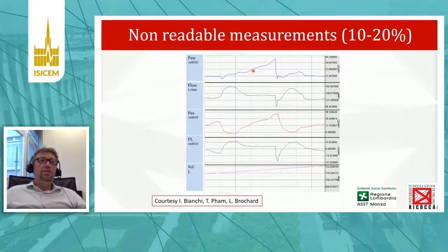And in this case, you will not be able to obtain a measurement of driving pressure. Still, it's better not to have a measurement than have a wrong one. In our experience, this occurs in 10 to 20% of the cases, and sometimes you can repeat the hold, obtaining a better measurement.